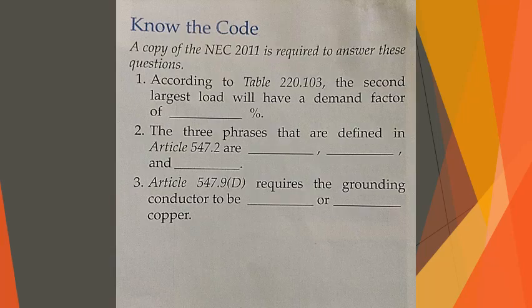Moving on to the Know the Code section. Question 1, according to Table 220.103, the second largest load will have a demand factor of 75%. That is on page 70-76 of the 2014 NEC.